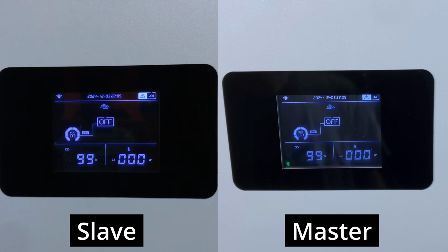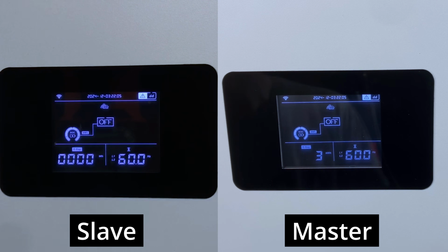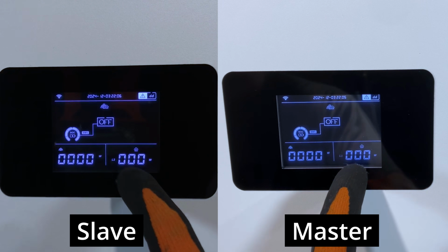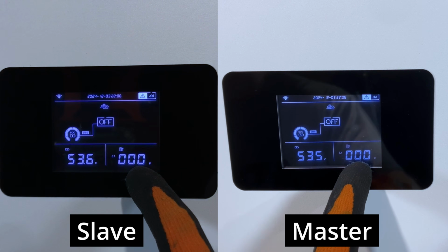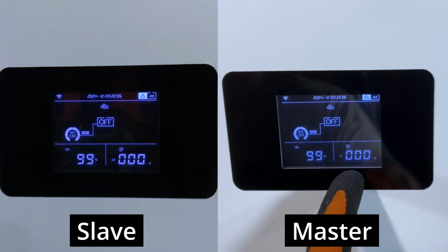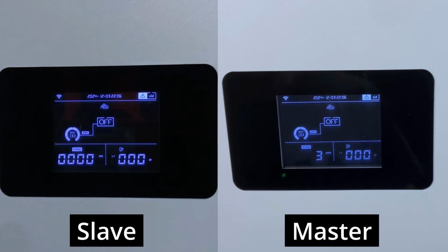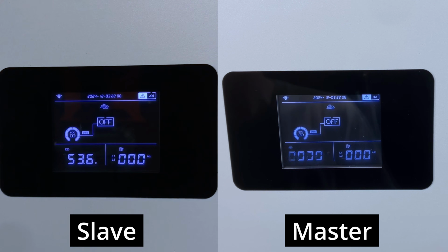I should be able to press the power button on either inverter, and then you'll start to see a countdown happen in the corner, and it should be pretty close to synchronized at about 10 seconds apiece. Let me press and hold the power button to turn on the master inverter, and we should see it start to count down. The output breakers are still turned off. So press that button, you'll hear a beep.